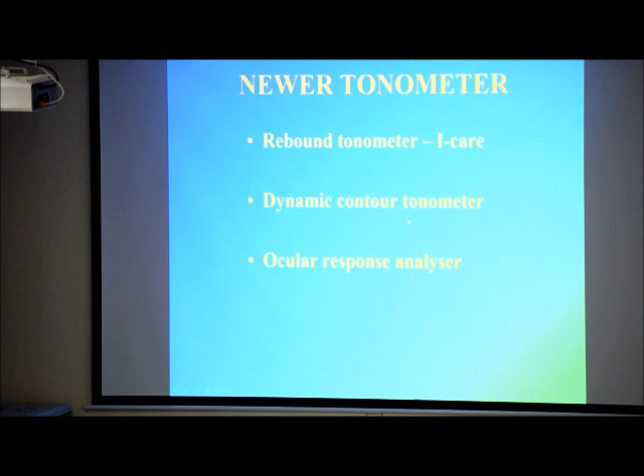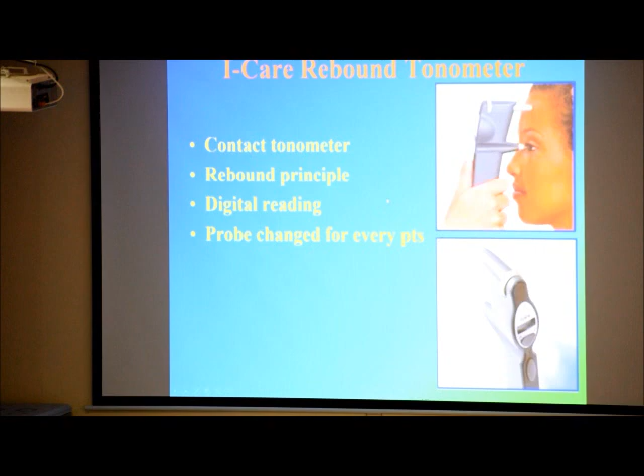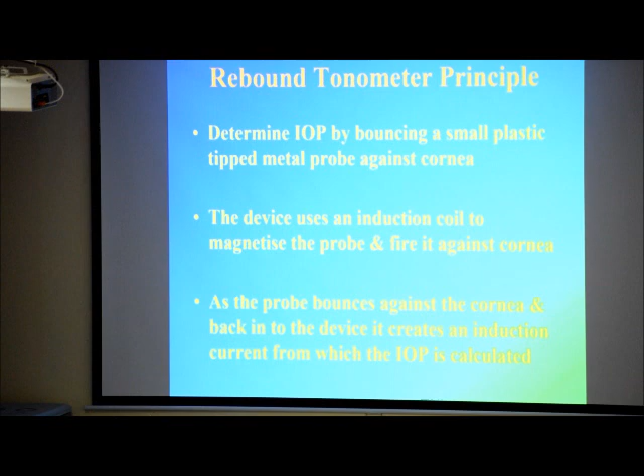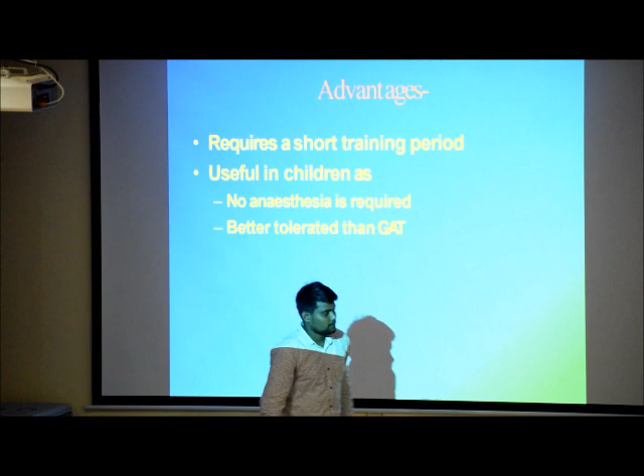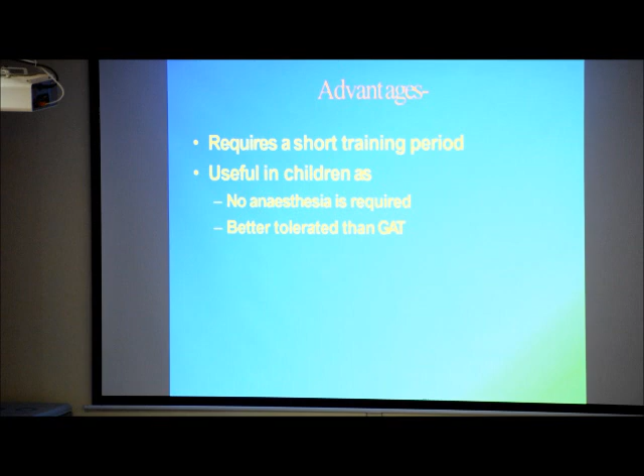The iCare or rebound tonometer is an indentation, contact tonometer. It is based on the rebound principle and provides a digital reading, and the probe has to be changed for every patient. The principle is that it determines the intraocular pressure by bouncing a small plastic-tipped metal probe against the cornea. The device uses an induction coil to magnetize the probe and fire it against the cornea. As the probe bounces against the cornea and back into the device, it creates an induction current from which intraocular pressure is calculated. It requires a short training period and is useful for children, as no anesthesia is required, and it is better tolerated than the Goldmann.